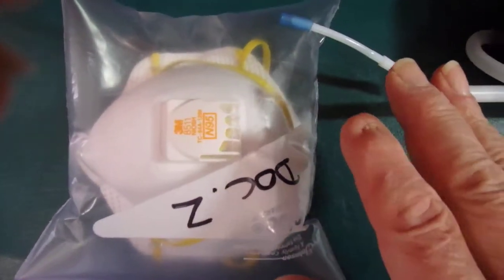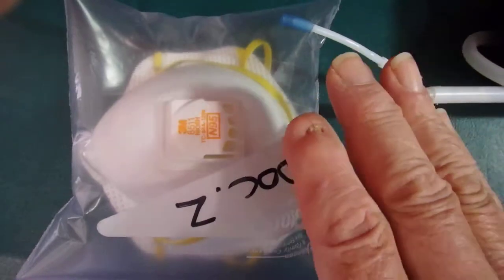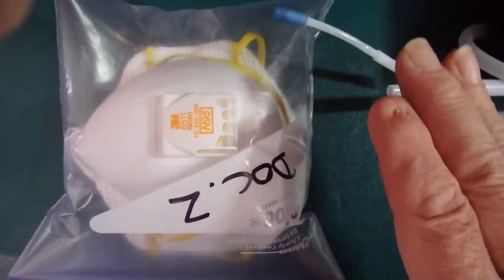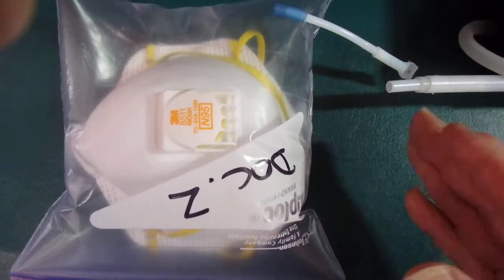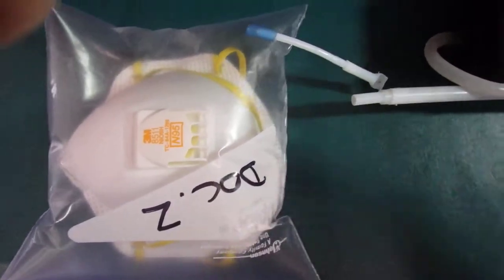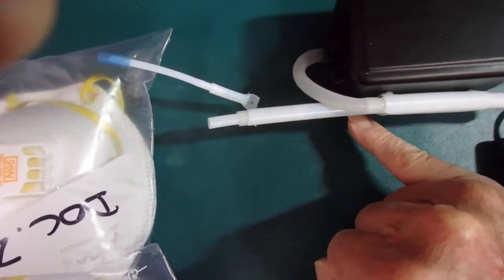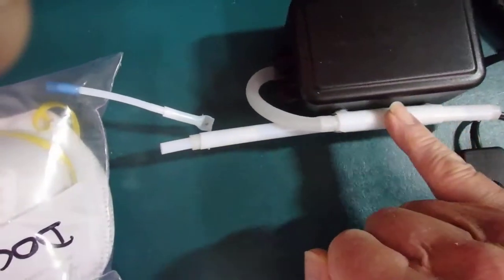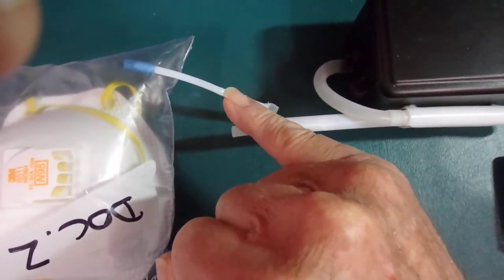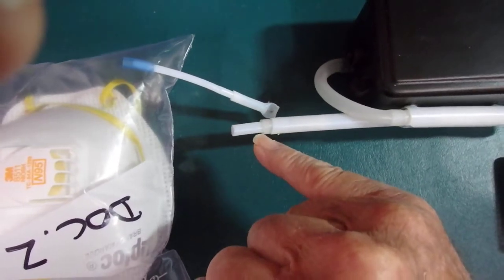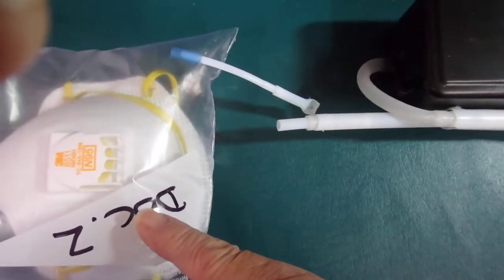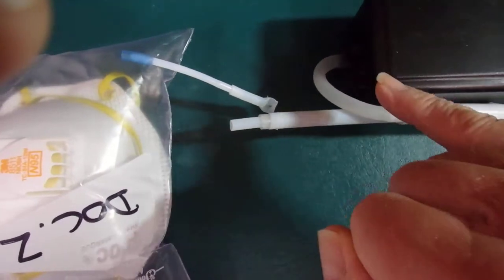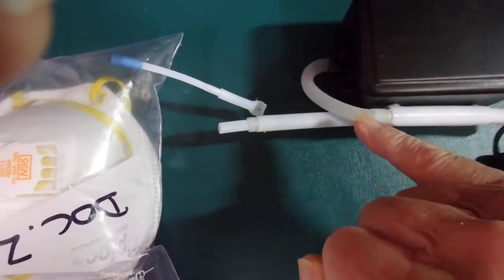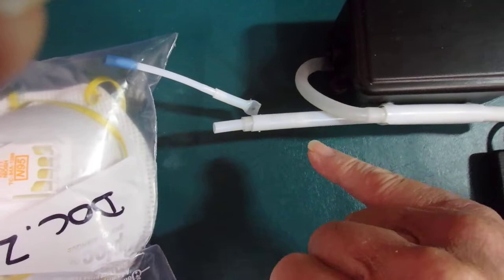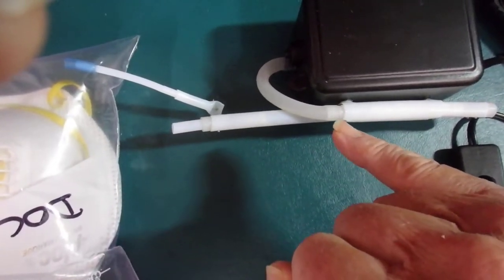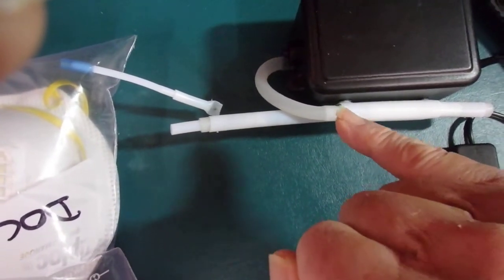Now, in order to evacuate the ozone without having any ozone in the ambient area of the room, and without having to go outside, we have a pump that consists of a destructor and a muffler. You connect the probe into the pump and it sucks out all the ozone inside the bag, then it goes through the destructor to the pump, and that way it exhausts only ozone-free gas into the room.